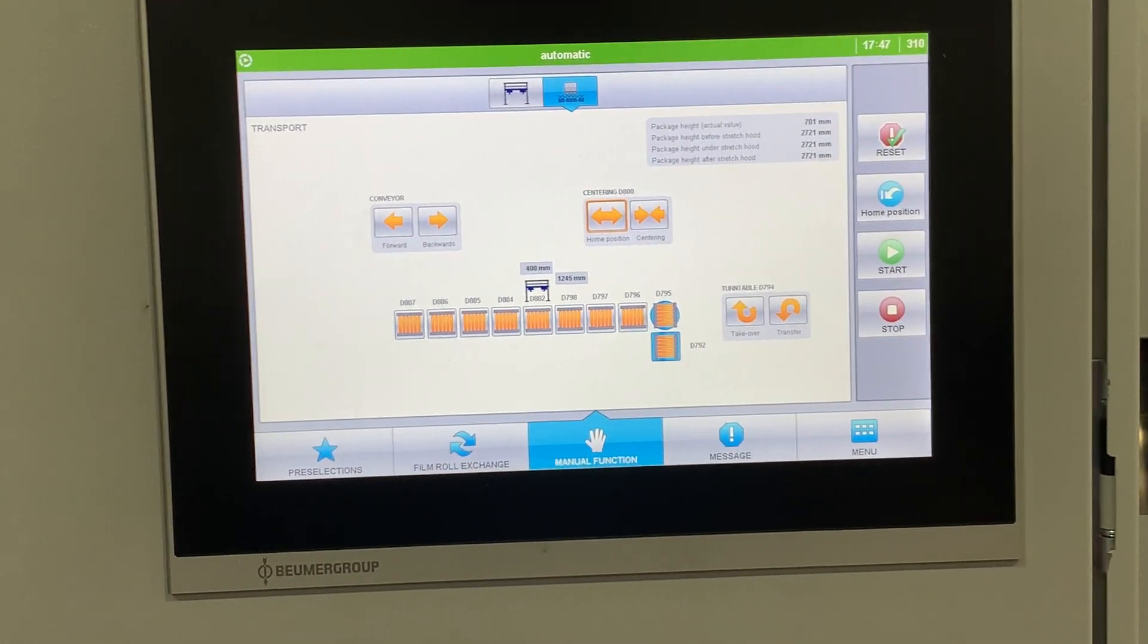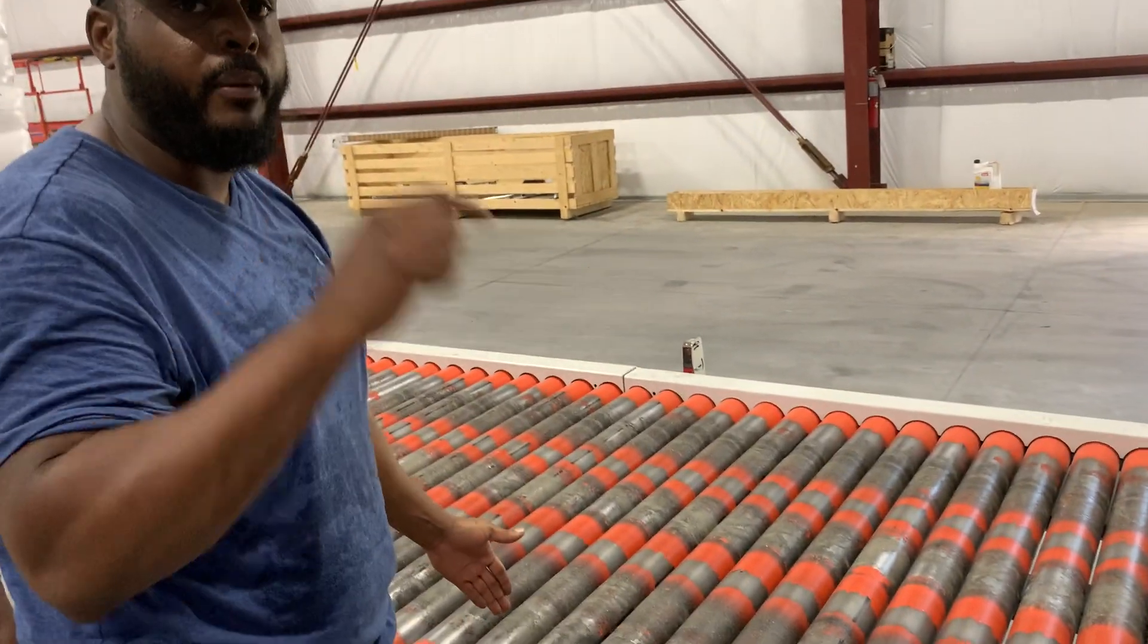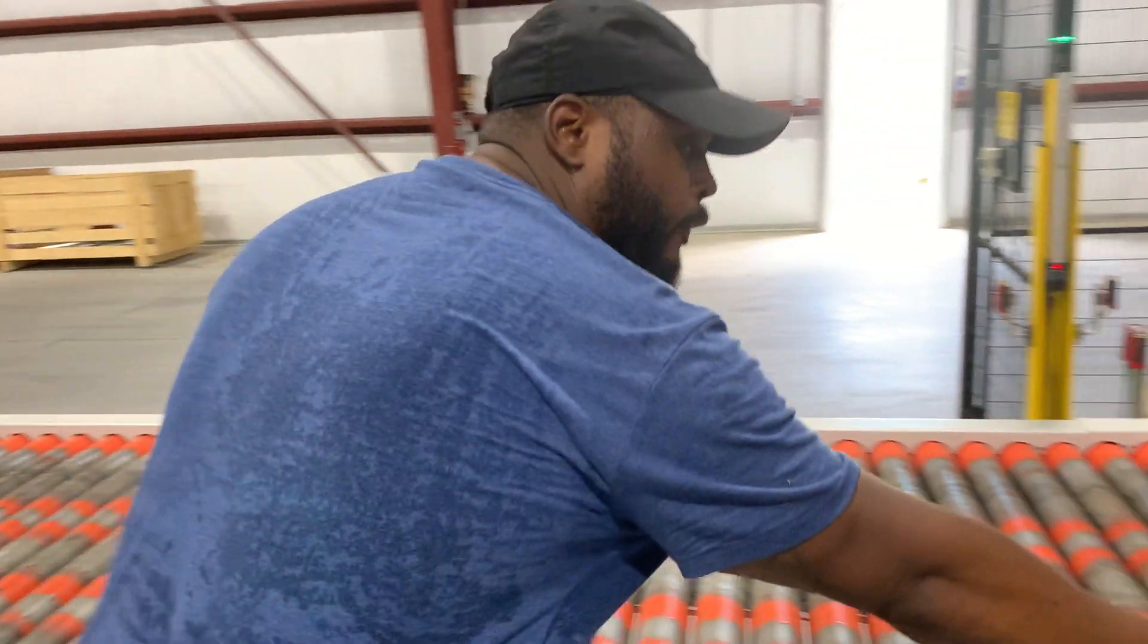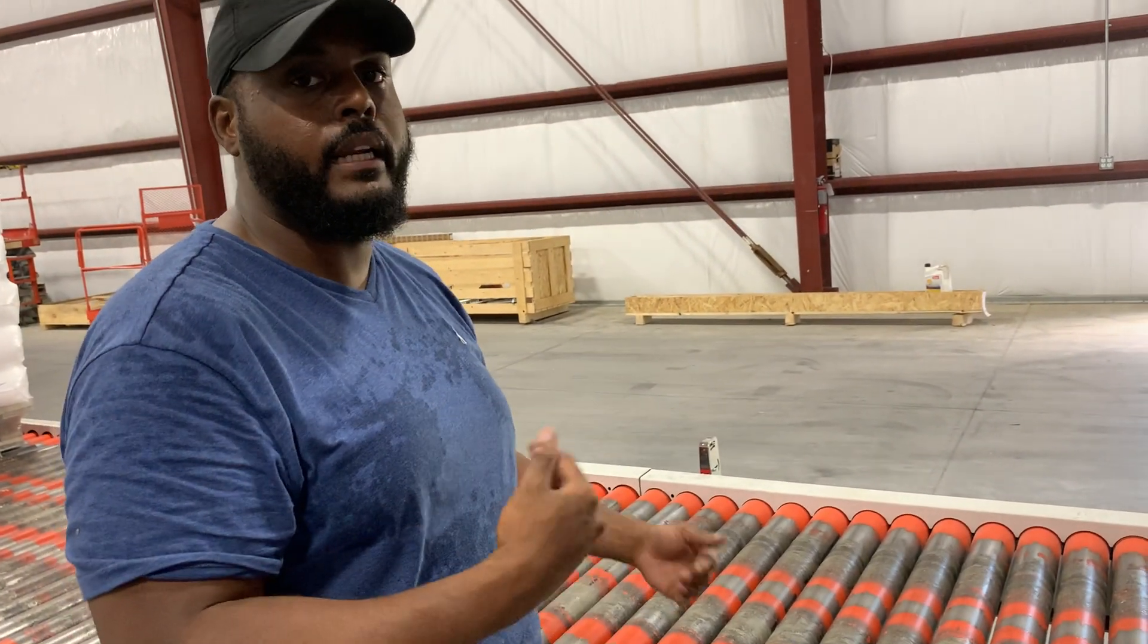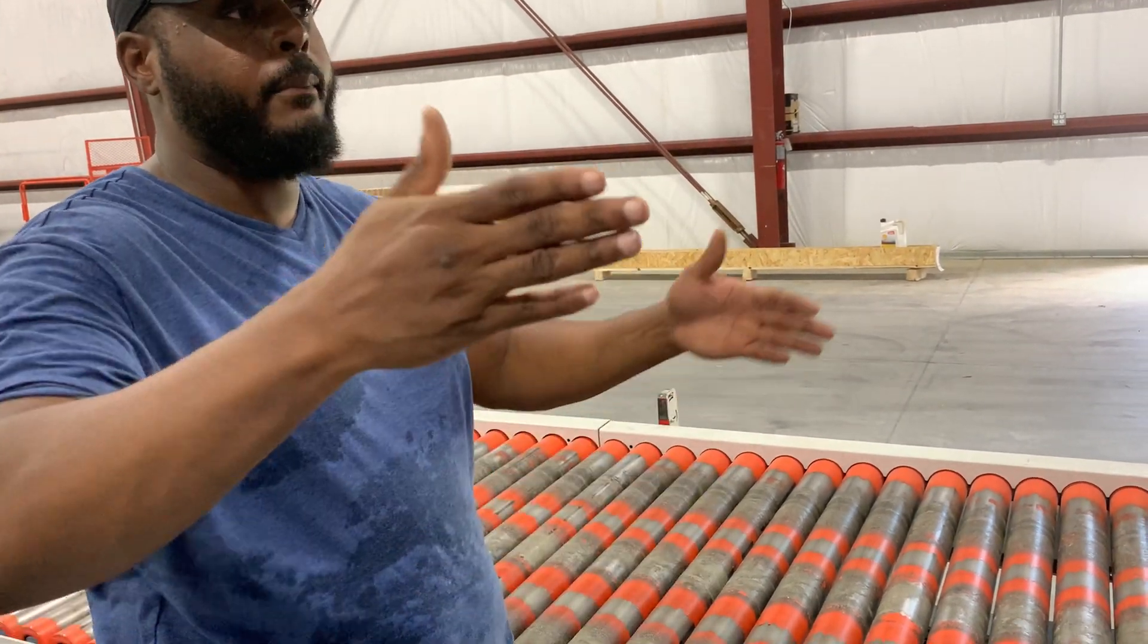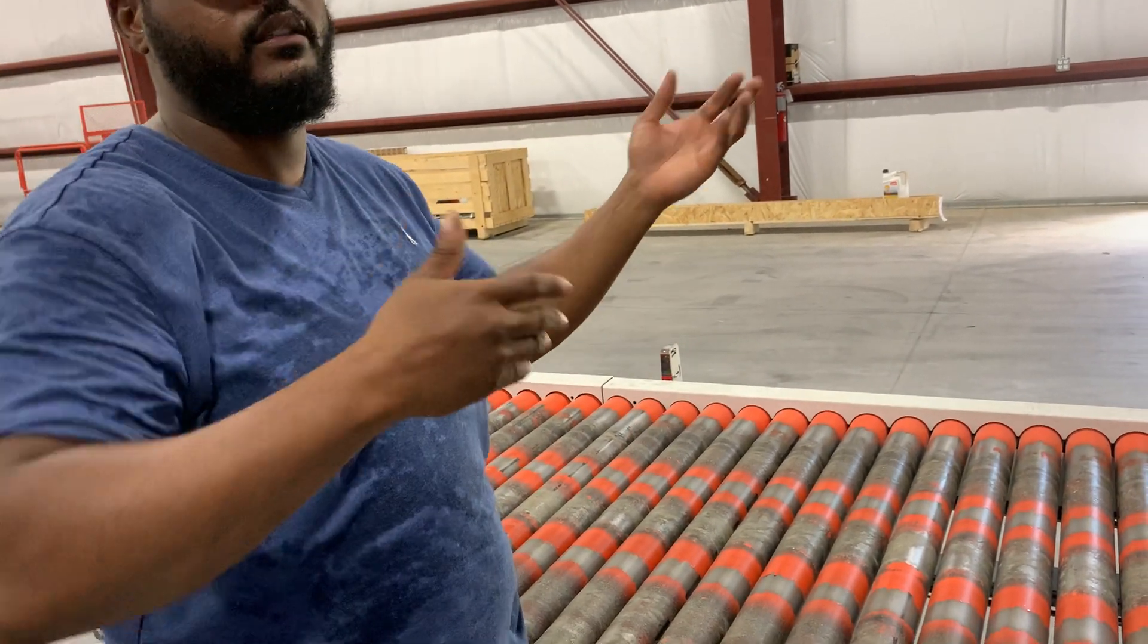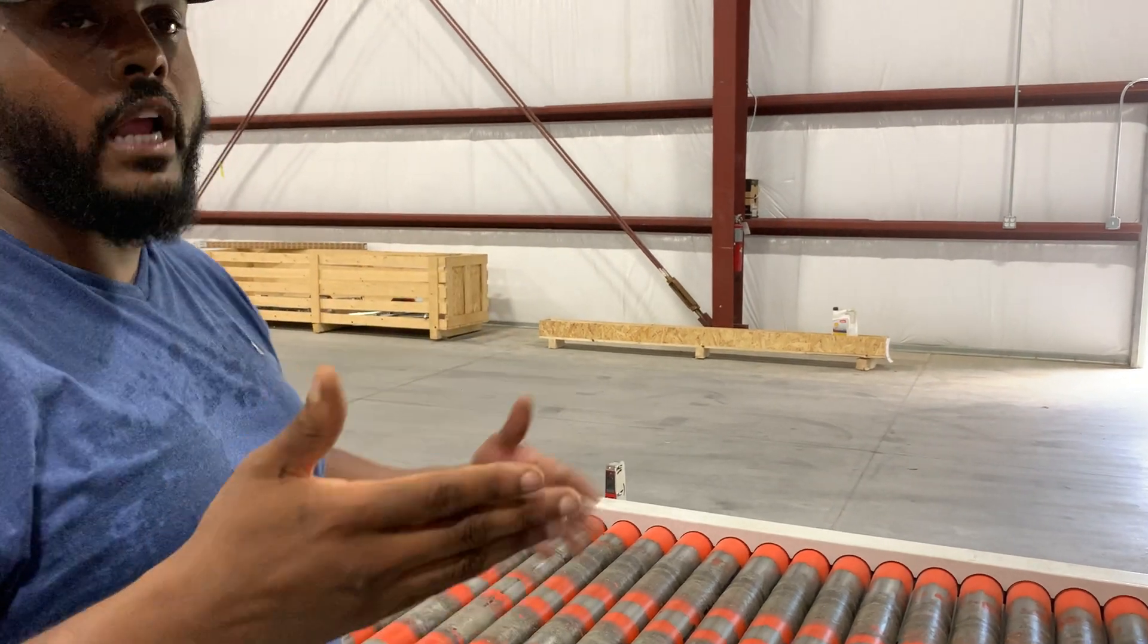We still need it. If that happens where the pallet is halfway through there, the only way to get out of that is to go to the manual function, turn on these two things and bump the conveyors forward. That's the only way. Because if we got a pallet in the middle of the transport and I stop my pallet right here, it happened to be in my photo eye.